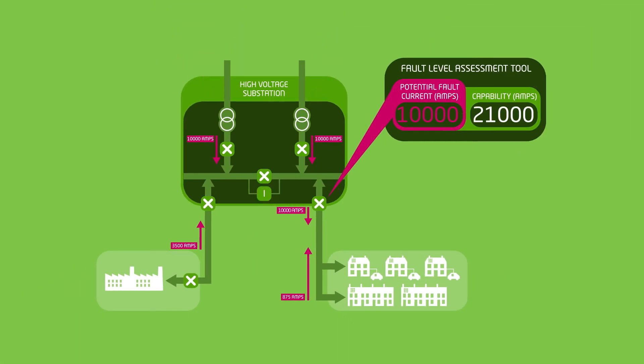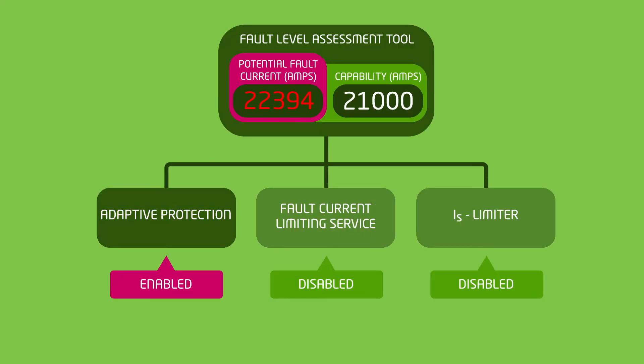As current on the network fluctuates throughout the day, RESPOND's fault level assessment tool will calculate potential maximum fault current. If the fault current exceeds the capability of the assets, one of the three techniques will be enabled, ready to operate in the event of a fault.